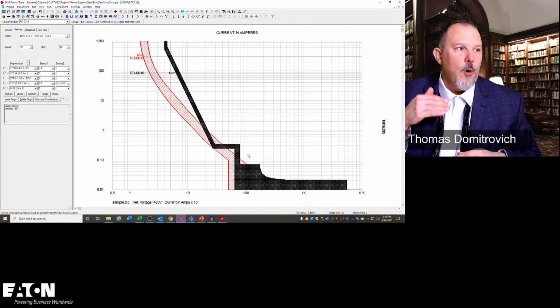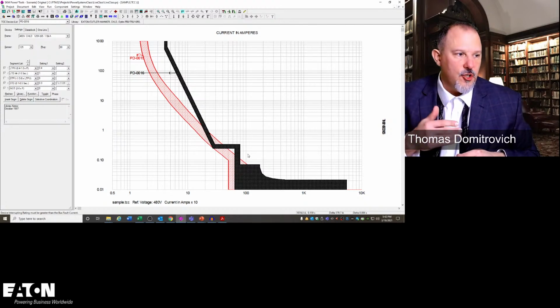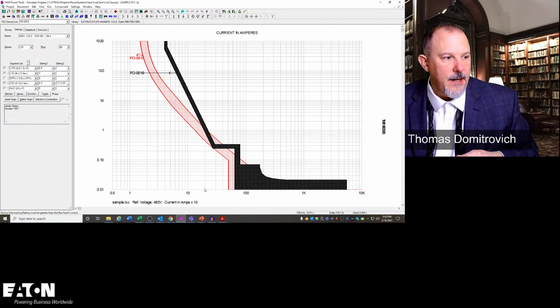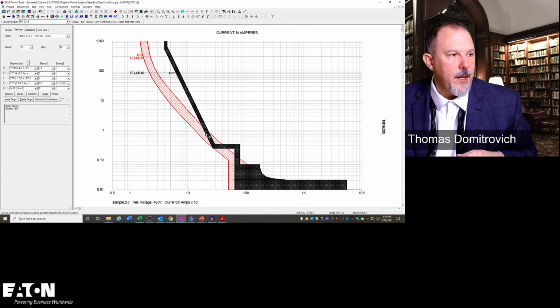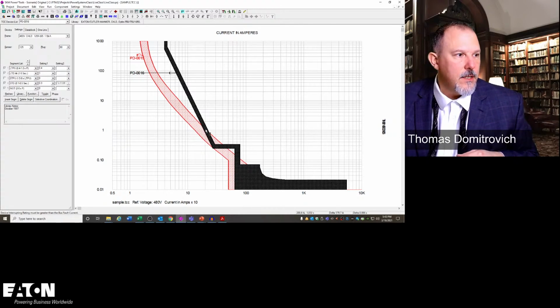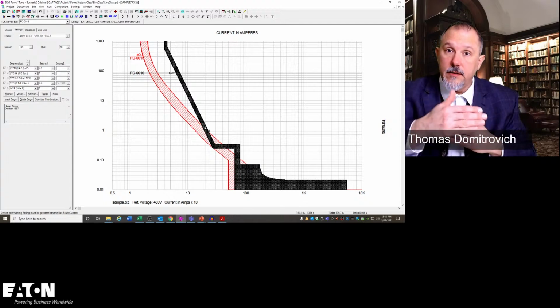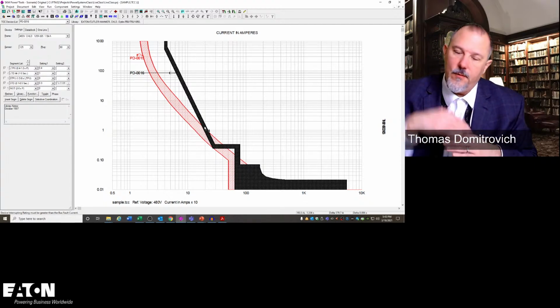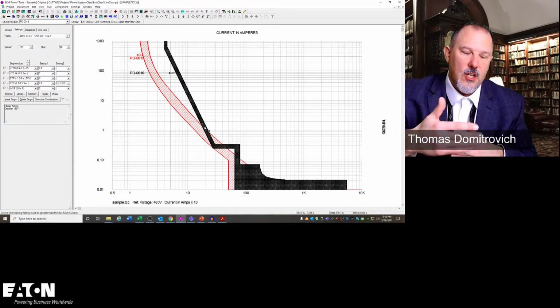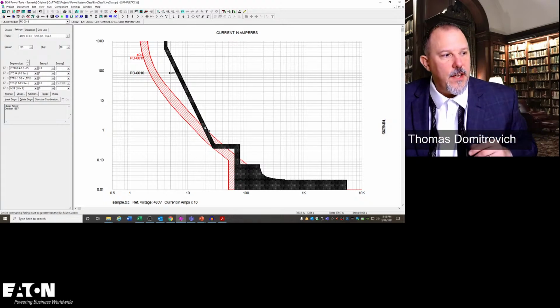So what we would say is on this trip curve, for say this value right here, it is 197 amps. If I follow it up, it'll trip anywhere from 0.798 seconds to 1.589 seconds. Okay, and we use those two clearing times to help us. From an incident energy perspective, we always use that top end. But the band helps us figure out selective coordination.